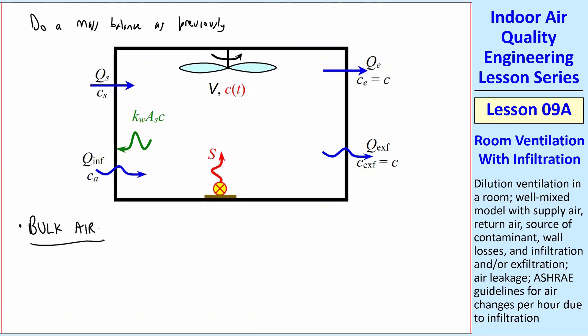For the bulk air, we have conservation of air volume flow rate. We'll assume the densities are pretty much constant, even though the temperatures can be different. So use an average density. So Q_S plus Q infiltration must equal Q_E plus Q exfiltration. We have two sources into the room of bulk air, and we have two sinks out of the room of bulk air.